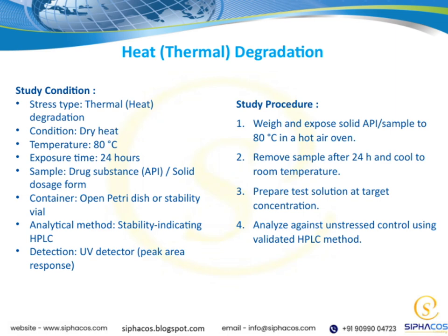The samples can be drug substances or solid dosage forms, placed either in open Petri dishes or stability vials to ensure proper exposure. The analytical method we use is a stability indicating HPLC, which is essential because it can accurately detect and quantify degradation products. Detection is achieved via a UV detector, focusing on peak area response to assess the extent of degradation.